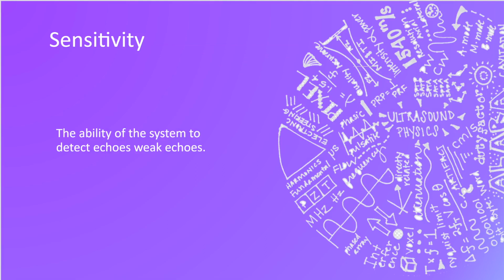Over the next few slides, we're going to talk about some of the things that we can test with our quality assurance program using our phantoms, specifically the tissue equivalent phantom. The first thing that we want to test is the sensitivity. And the sensitivity of the machine is the machine's ability to detect weak echoes.